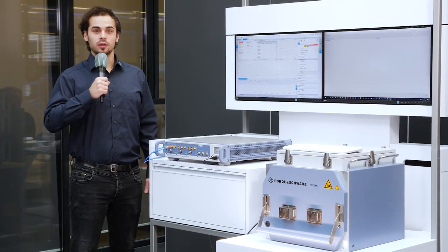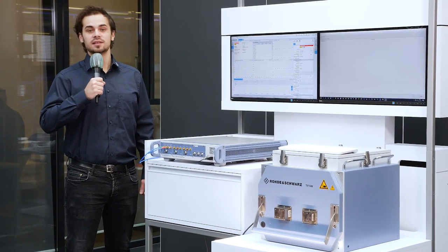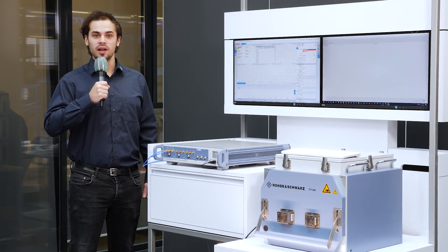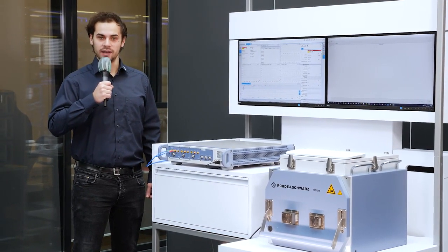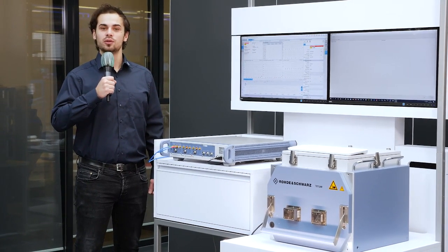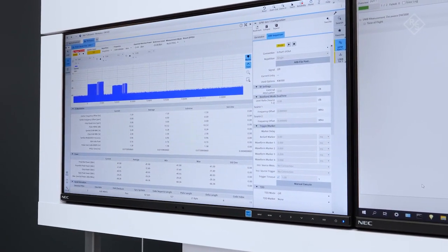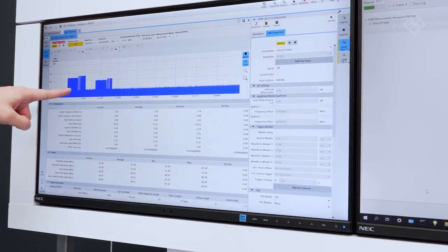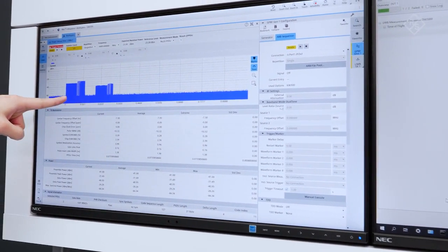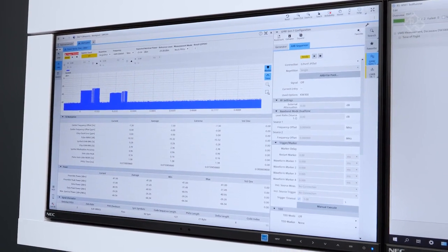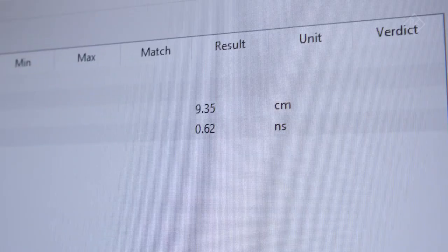With this setup, you can do RX test cases, TX, angle of arrival, and also the important time of flight measurement. Let me demonstrate the time of flight measurement. In the power versus time window, we can see the two messages that got exchanged between the DUT and our instrument. And in our WMT tool, we can calculate for distance and for the time.